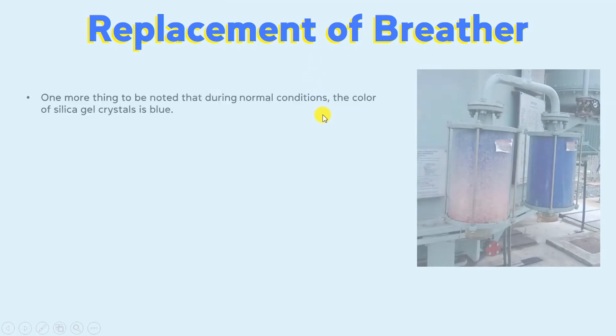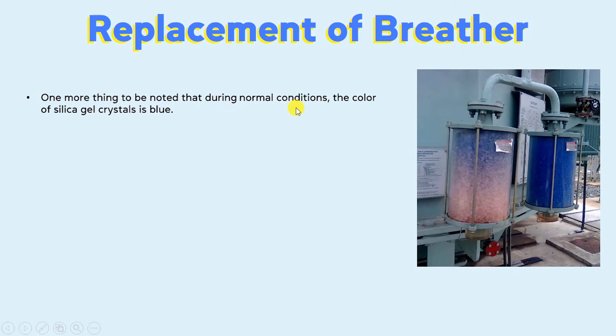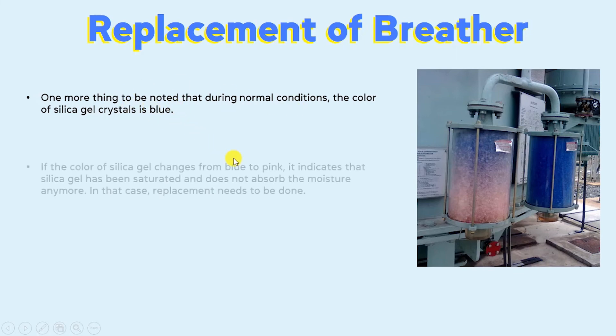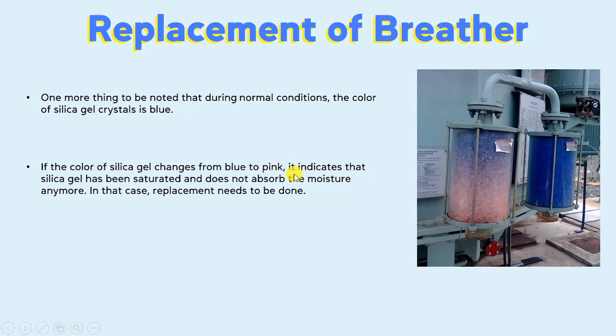Replacement of Breather. One more thing to note: during normal conditions, the color of silica gel crystals is blue. If the color of silica gel changes from blue to pink, it indicates that the silica gel has been saturated and does not absorb moisture anymore. As you can see in the diagram, during normal conditions the color of silica gel crystals is blue. However, if the color changes from blue to pink, it means the silica gel crystals are unable to absorb moisture from the atmospheric air. In that case, replacement of the breather needs to be done for proper absorption of moisture, so that it doesn't affect the insulation properties of transformer oil.